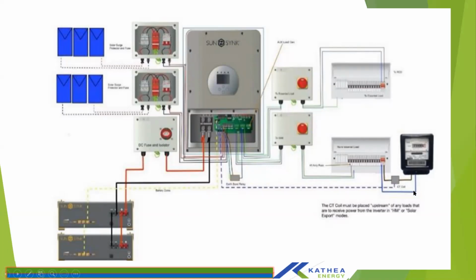And then from your grid incomer, you supply your DB board, your main loads, your non-critical loads, and then the same line goes to the inverter, preferably through an AC protection box as well. And then the output of the inverter, which is the essential loads connected on the load port on the inverter, will then be wired to the non-essentials through an AC protection box as well.